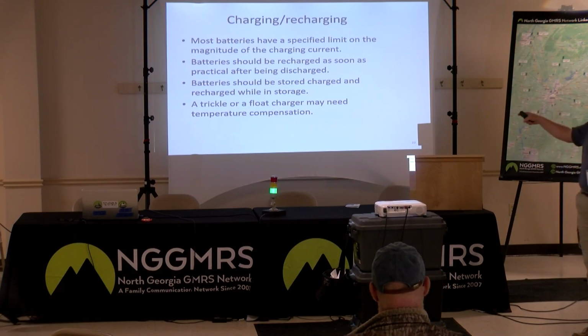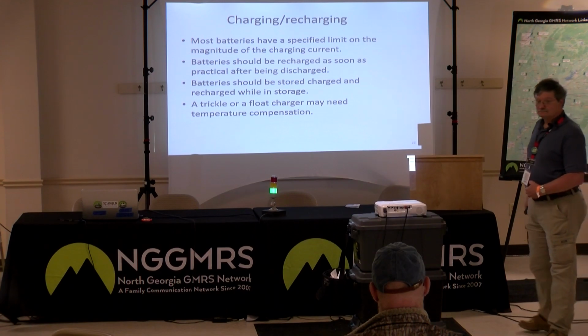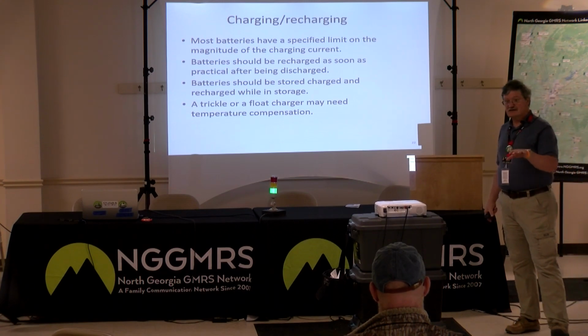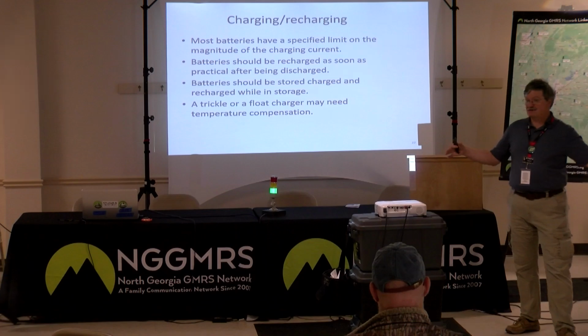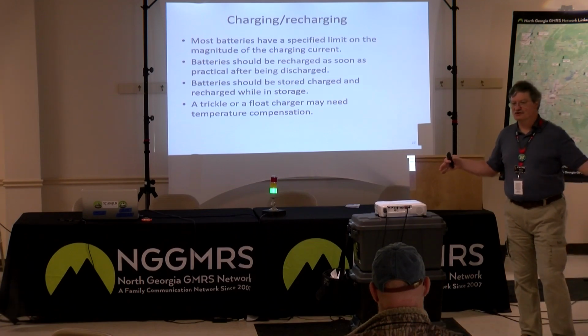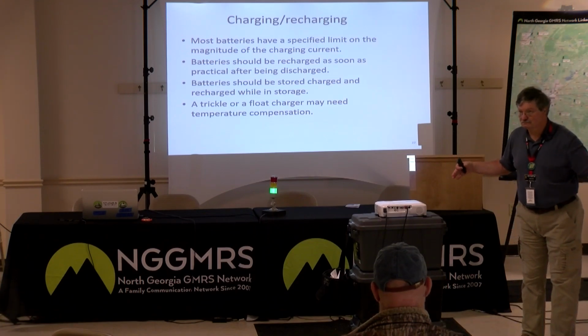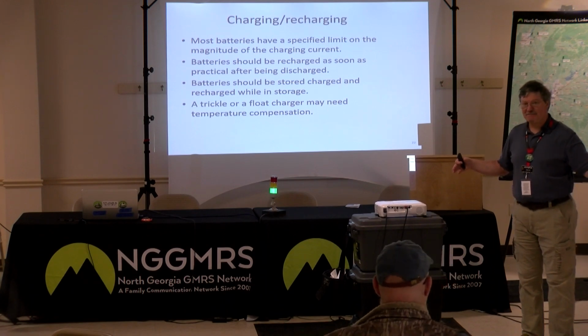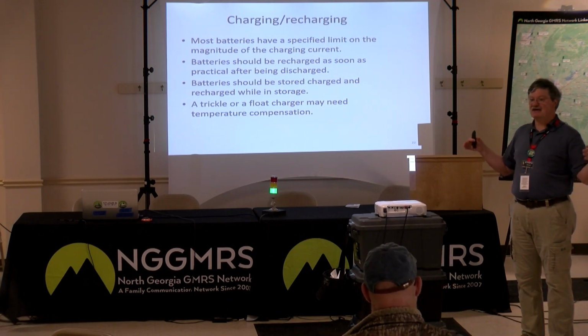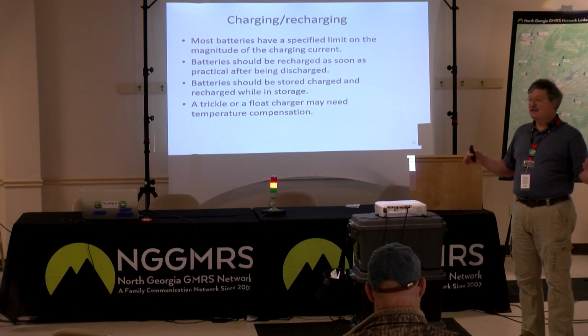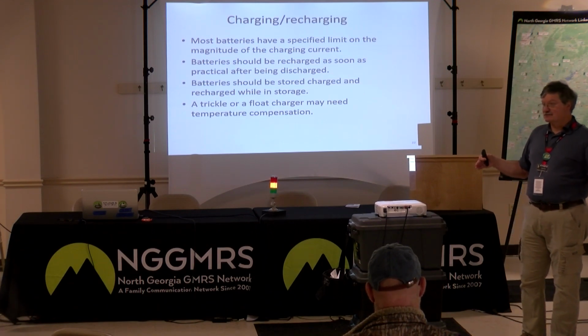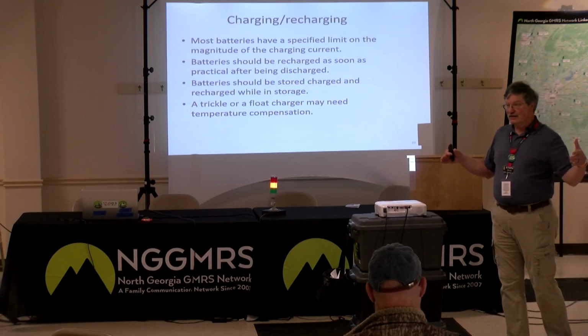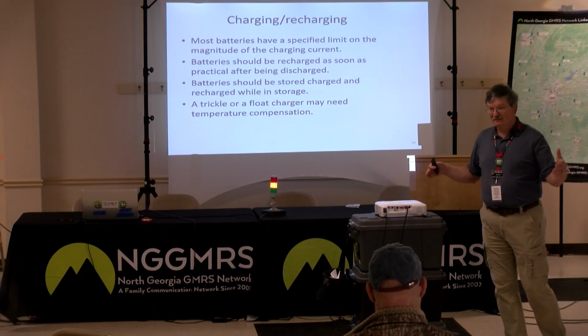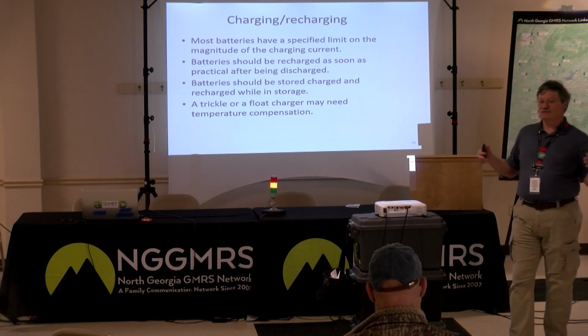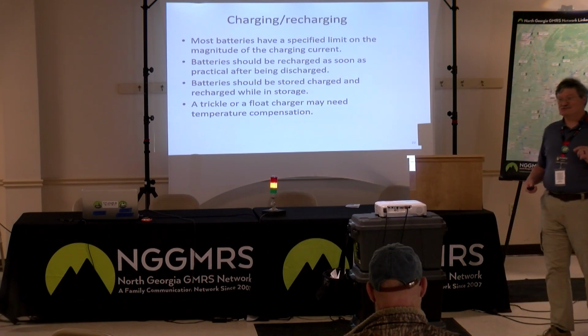You can use a trickle charger or float charger. Utility companies have batteries that are always on charge - they call it float. So if something happens, that battery is at full capacity. If they've got an 8-hour battery, that battery should go 8 hours. It's not 7 hours and 28 minutes or 7 hours and 49 minutes - it should go the full 8 hours because it's at a full state of charge.